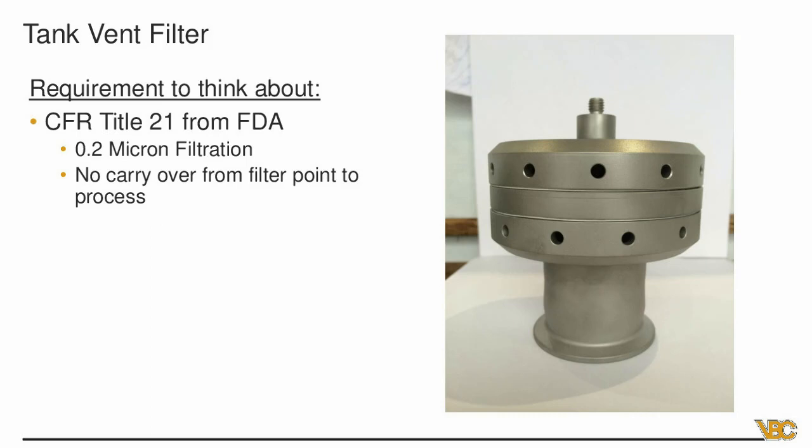The cleaning cycle is really dependent on how clean or dirty your supply is. So in an air example, how clean or dirty your air supply is really going to dictate how often you have to clean it. But realistically, you should be talking about a week to a month before you need to clean these things, depending on how big or small your process flow is. It might be more prudent for you to clean after every batch, or you might just put it into your regularly scheduled maintenance, once every 2 weeks or once every month, to run it through a cleaning cycle.